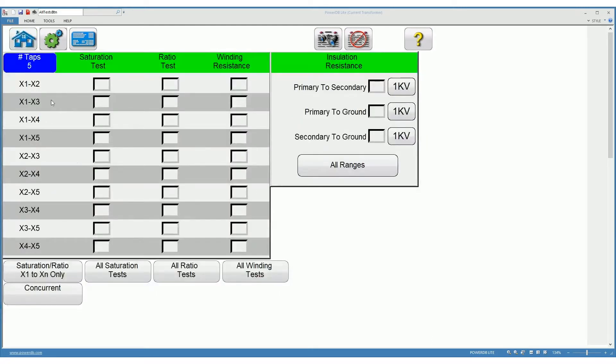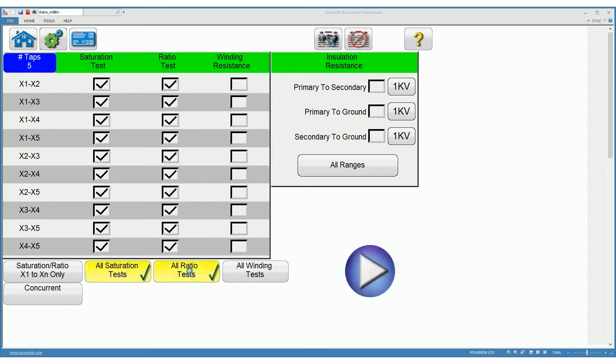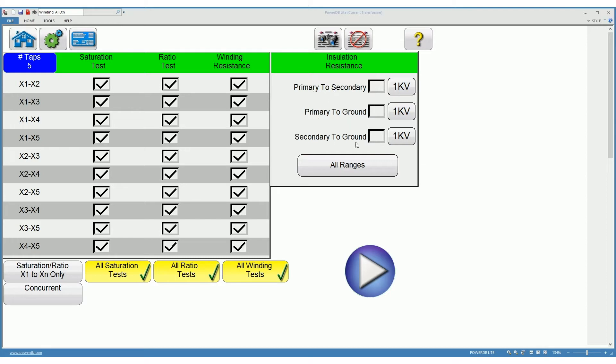In this case we will be testing a 5-tap CT. We can select all the saturation, ratio, and winding resistance tests as well as the insulation resistance tests for primary to secondary, primary to ground, and secondary to ground.